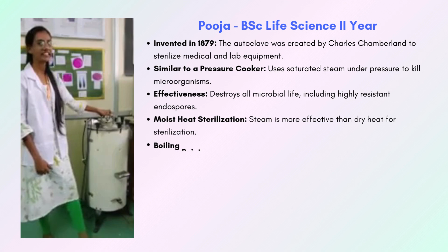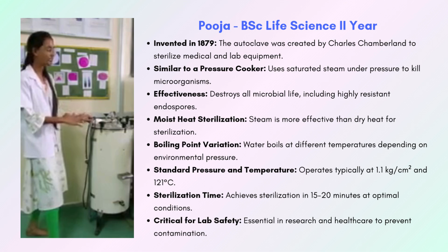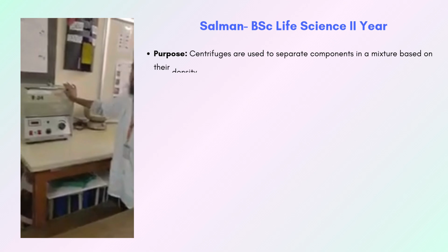The boiling point of water varies depending upon the surrounding environmental pressure. The usual procedure is to heat at 1.1 kilograms per centimeter squared steam pressure, which gives a temperature of 121 degrees Celsius. At 121 degrees Celsius, autoclaving to achieve sterilization takes 15 to 20 minutes, depending upon the volume of the load. So here is the equipment called centrifuge.